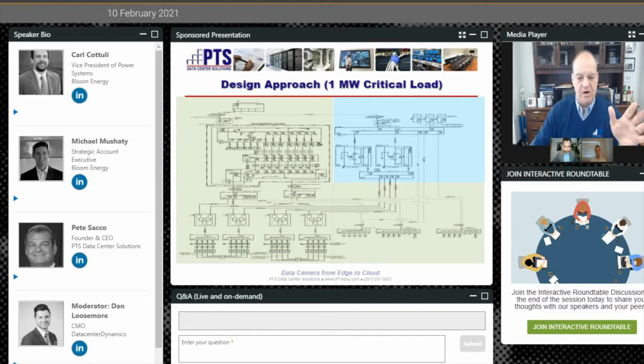This eyesore is the very complex electrical one-line diagram for a 1 megawatt design that's in process. I'm putting it up because I want to make a point. The green is what you would need for the tier two part of the load. The blue is the only piece you would add if you want 2N. In this particular design, I am indeed 1 megawatt, but everything in the square box at the top, and everything below the utility service entrance in that dotted line box, is the Bloom Energy server.